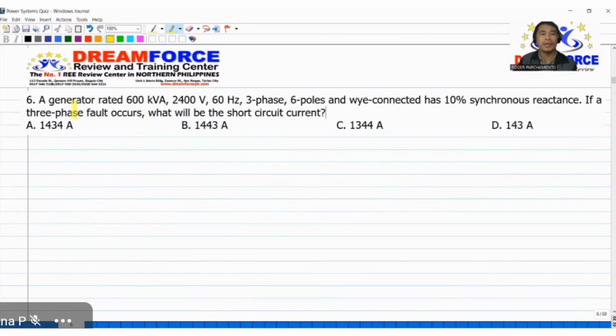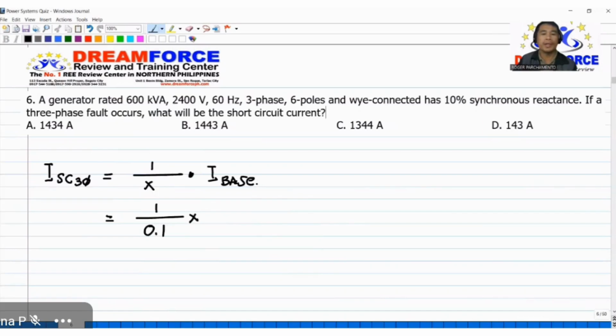Number 6. A generator rated 600 kVA, 2,400, 60 Hz, 3-phase, 6-pole, and Y connected, has 10% synchronous reactance. If a 3-phase fault occurs, what will be the short circuit current? Short circuit current for 3-phase is equivalent to 1 over X multiplied by I base. That is 1 over 10% or 0.1 multiplied by the base current is the 3-phase current. That will be 600 kVA. 600 times 10 to the 3, then divided by square root of 3 times the line-to-line voltage, 2,400.